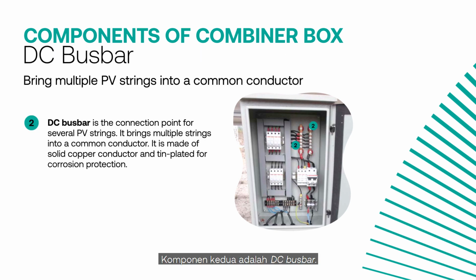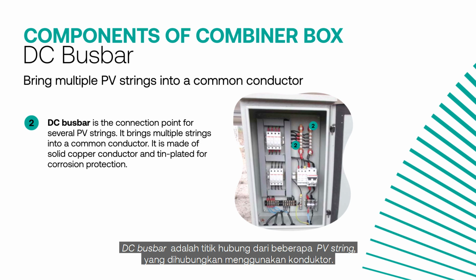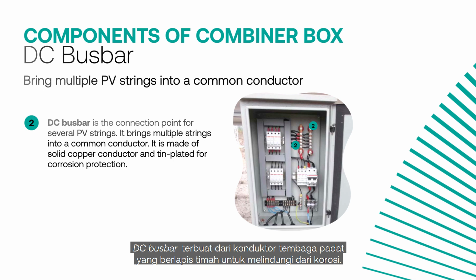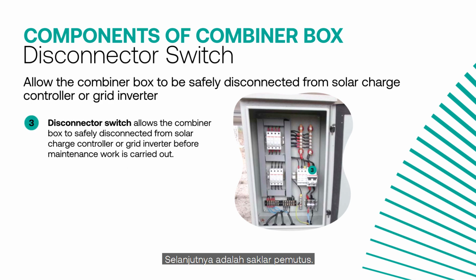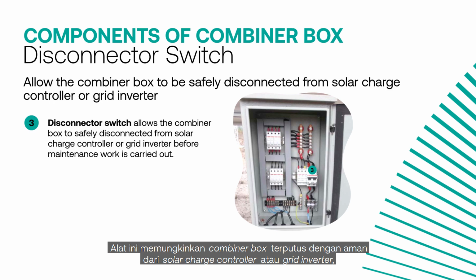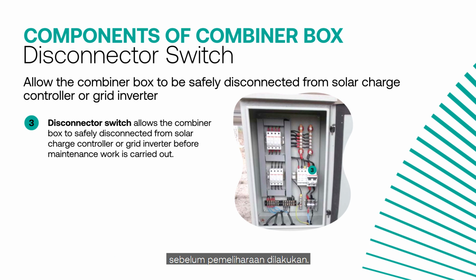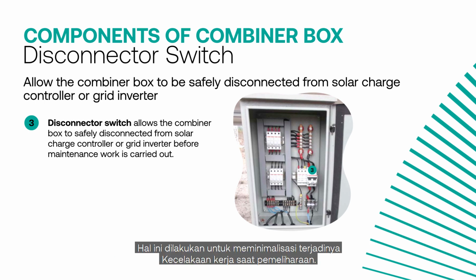The second component is the DC bus bar. The DC bus bar is the connection point for several PV strings. It brings multiple strings into a common conductor. It is made of solid copper conductor and tin plated for corrosion protection. Next is the disconnector switch. This device allows the combiner box to be safely disconnected from the solar charge controller or grid inverter before maintenance work is carried out. Hence, it will minimize the occurrence of accidents.